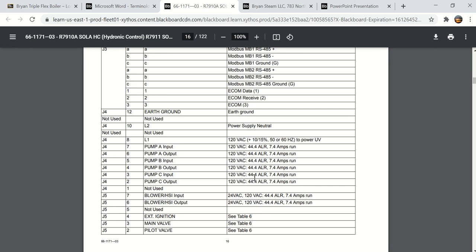And when you see the term amps, locked rotor amps, you think a motor. And yeah, you could directly connect a fan motor that had a full load amps of 7.4 directly to these contacts and stop and start it through that contact. Typically, that's not what you're going to see on a booster fan or combustion air damper. You would probably just run voltage through the contact, and then you would use a relay or a motor starter to turn something else on and off.